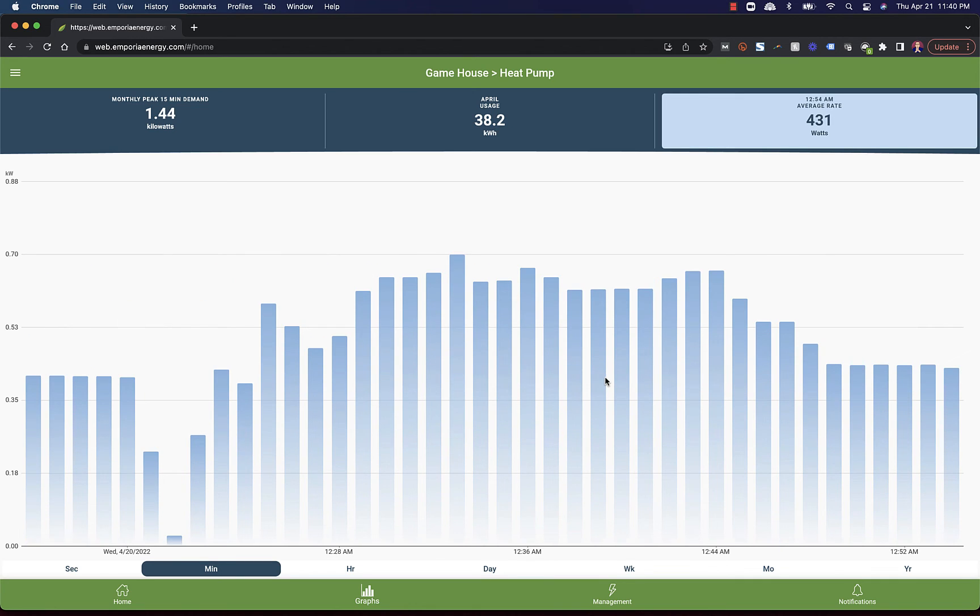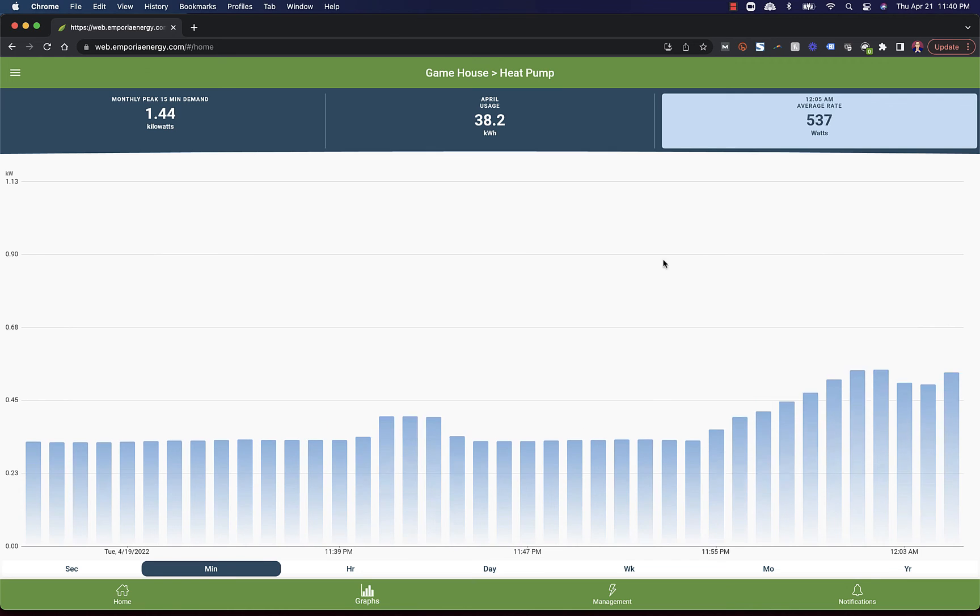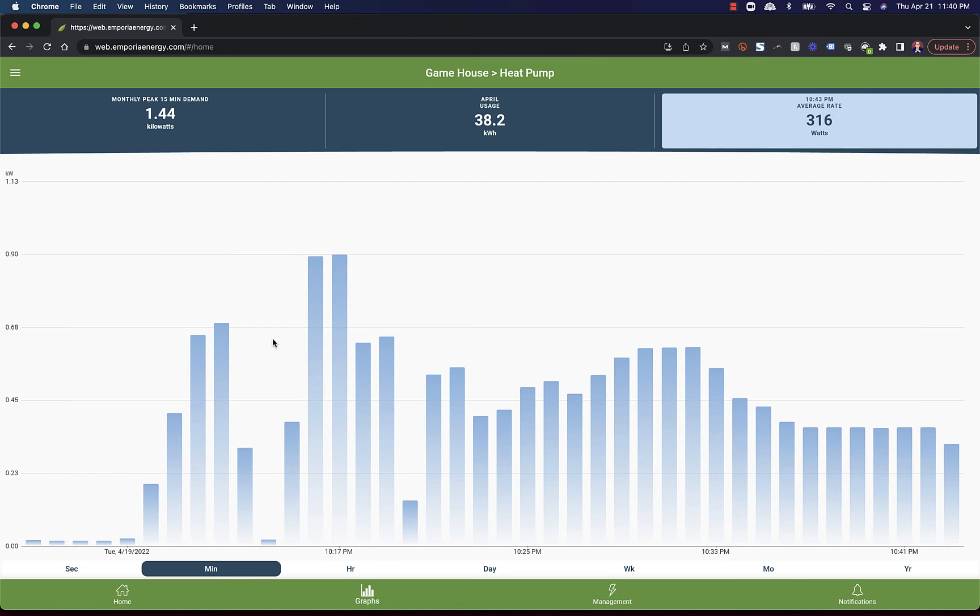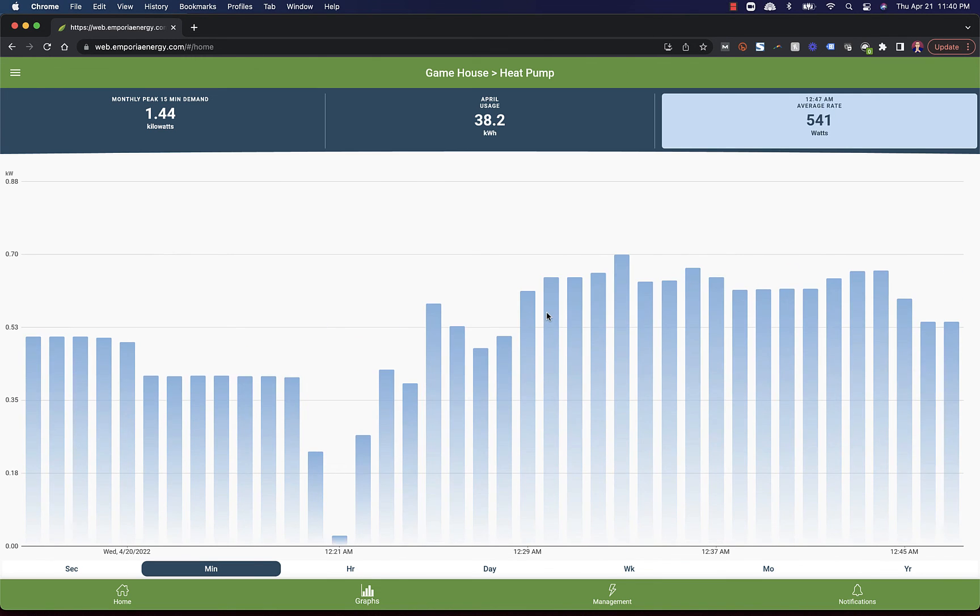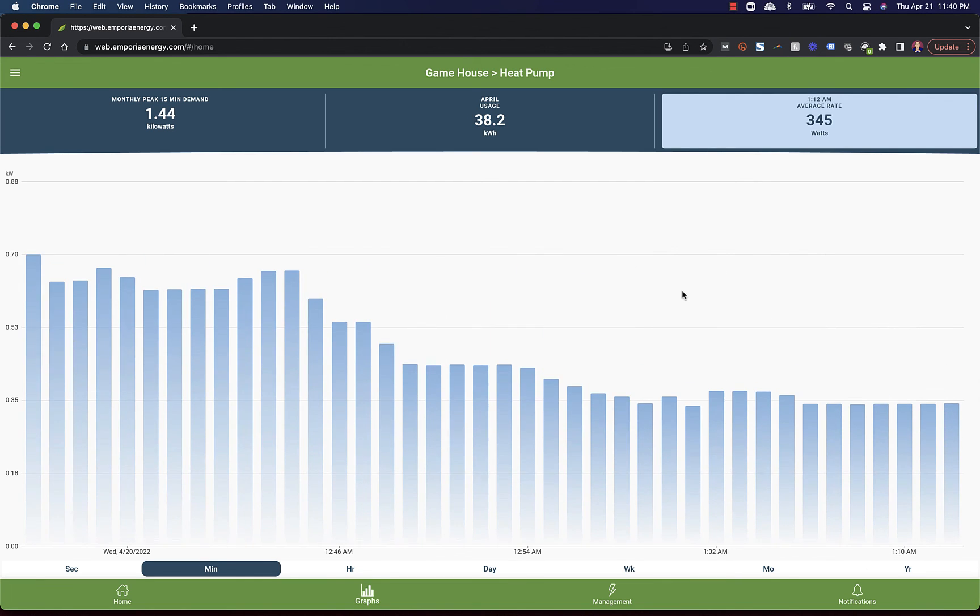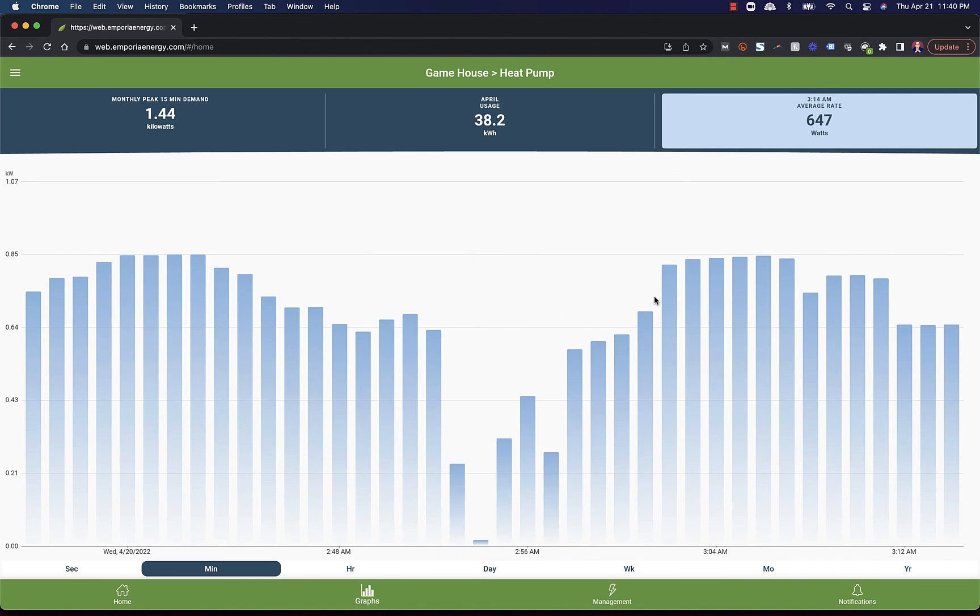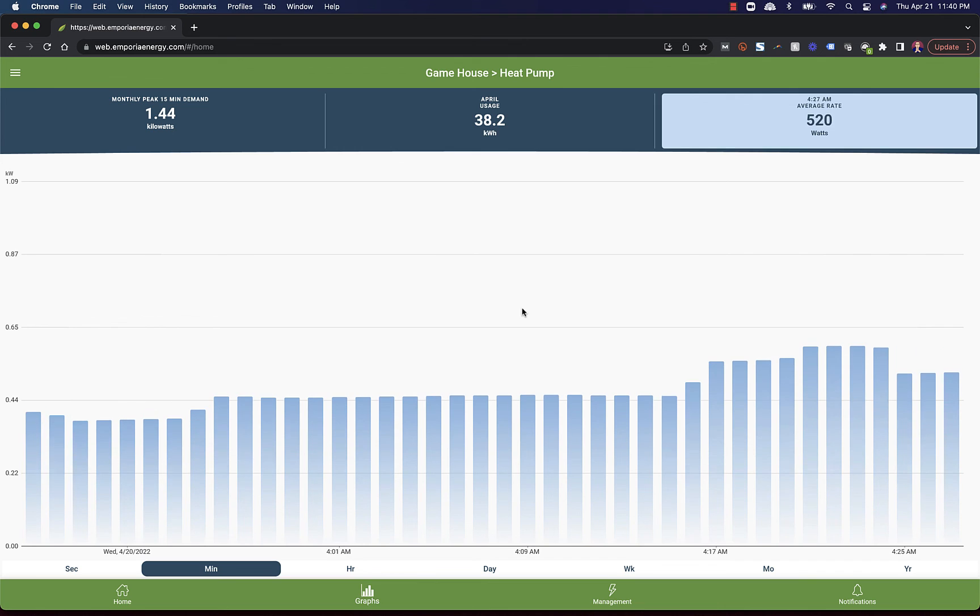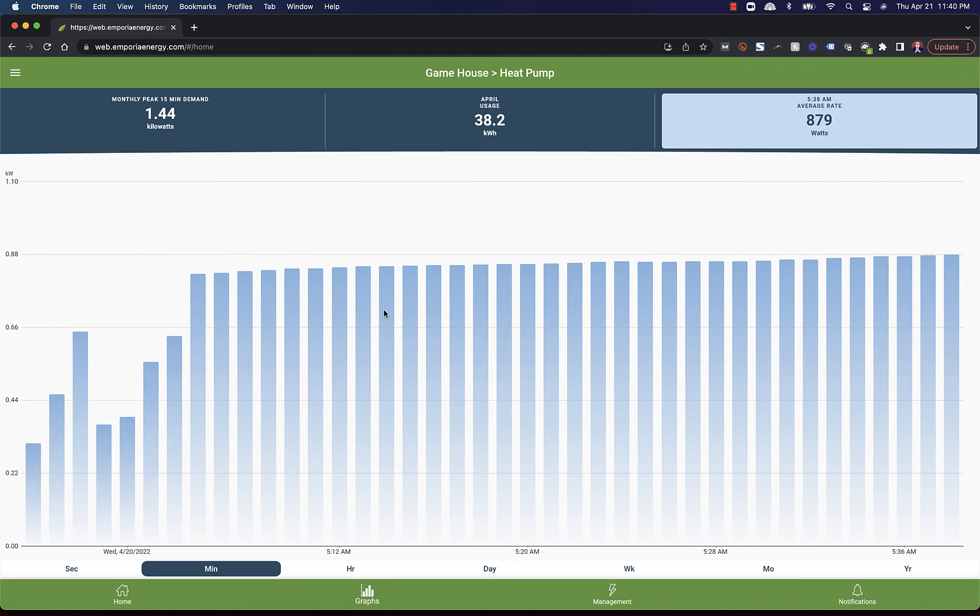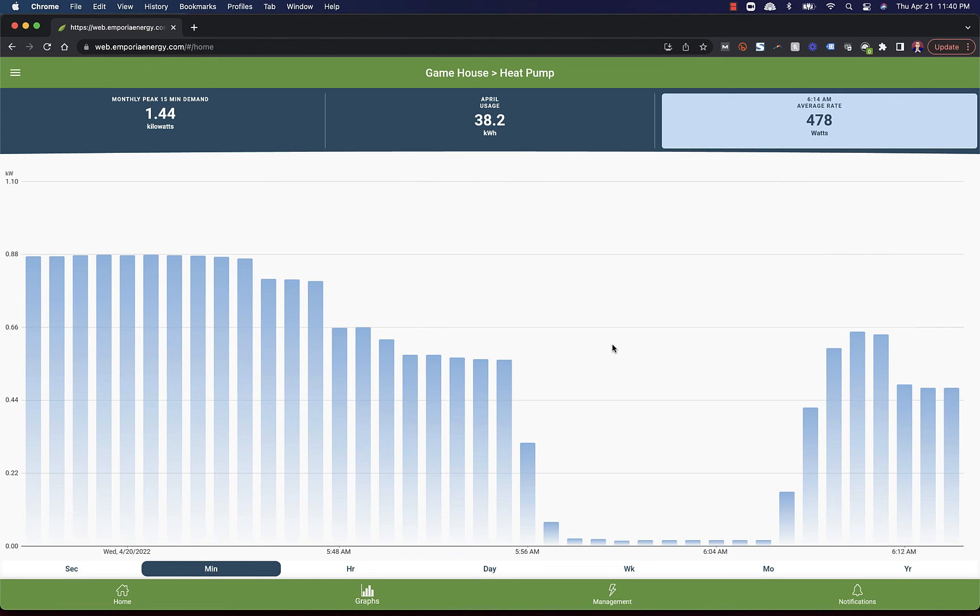And the Daikin Fit, it's not a particularly expensive system. It's substantially less than the Carrier Greenspeed I've been using for years. Yeah, look at that. That system, holy cow, wasn't it ever? So it turned on at what, 10, 10 p.m. And it's just running. It's running. There's the defrost cycle. It's running. So there's two hours. There's three hours. There's four hours. Another defrost cycle. Is that 10 o'clock? There's five hours. It ran all night. Look at that. Six hours. Seven hours. So after about eight hours, it finally shut off. That's incredible.